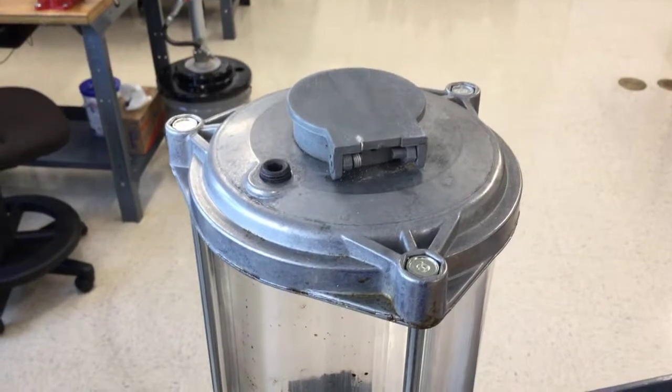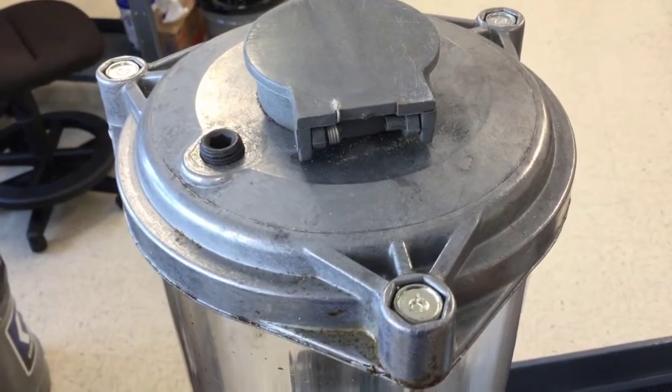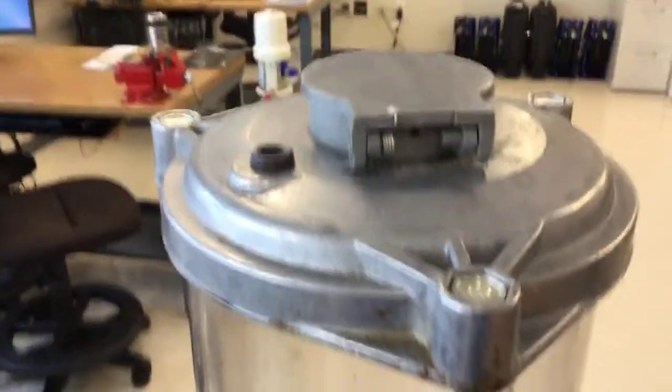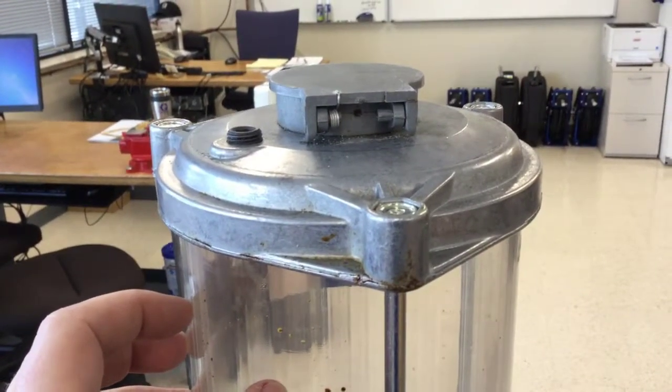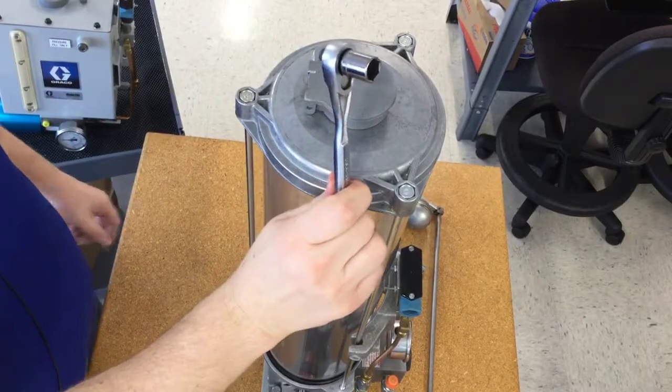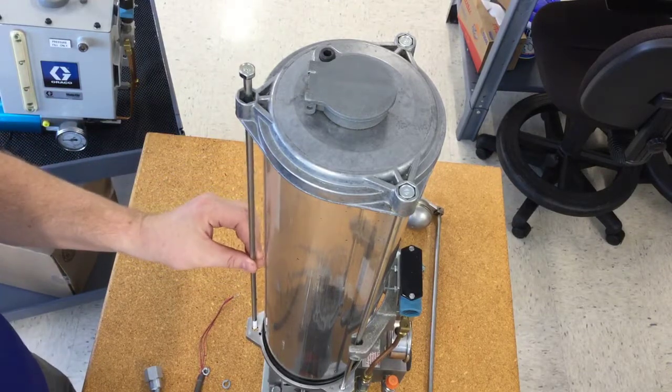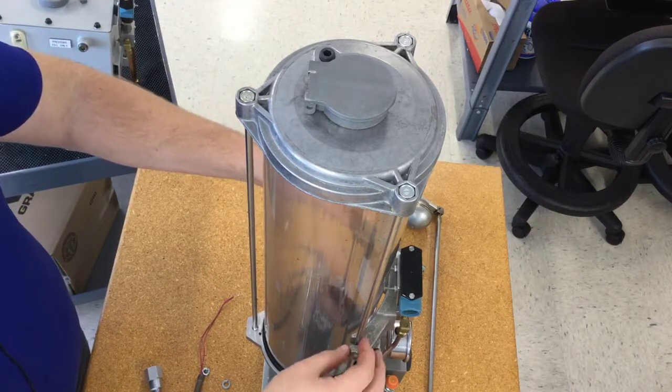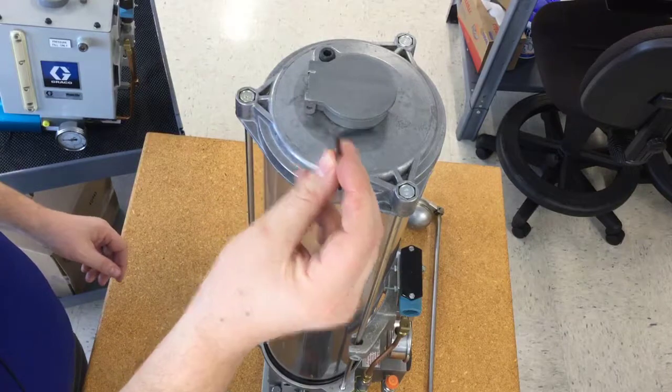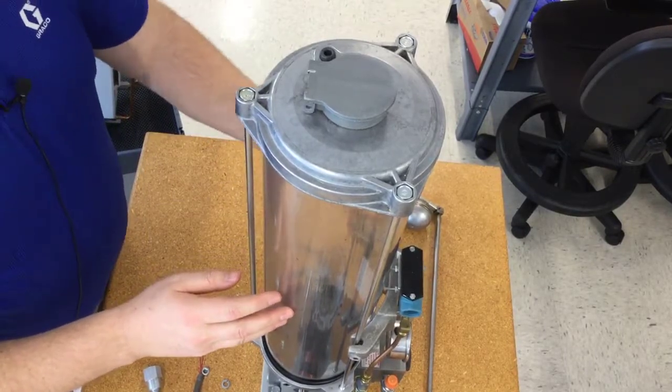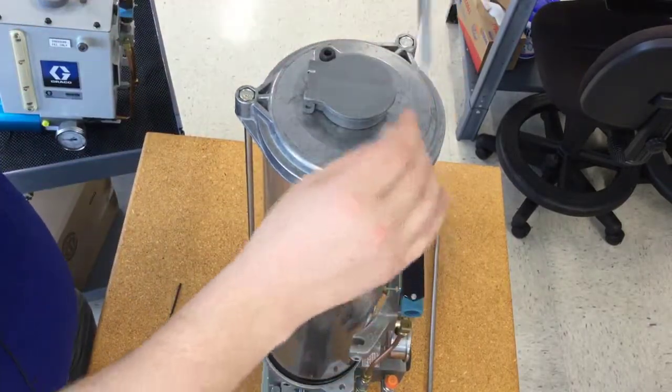But for these cylindrical reservoirs if you look here, these heads of the bolts are seated into the cover which means we got to come all the way down here to the bottom of the reservoir and take off the tie rod nuts. So we'll take the tie rod nuts off and then pull the tie rods up and out of the holes, but I'm going to try to leave the tube in place just so that it's one less thing to be rolling around on my workbench. I used a half inch ratchet to loosen the nuts at the bottom of the tie rods and then I removed the nuts and the lock washers and I should be able to just lift my tie rods out now. But my assembly also has a high pressure blowout switch on the front so now I need another tool. I need a one-eighth inch hex key to remove the bracket or at least loosen the bracket from the tie rods, and that's a real quick and simple operation and it'll just hang here on the tubing, that's fine. Now we can lift our tie rods up and out.